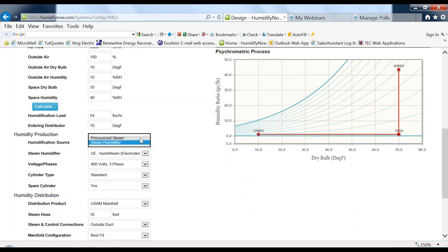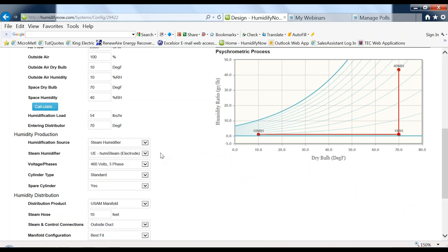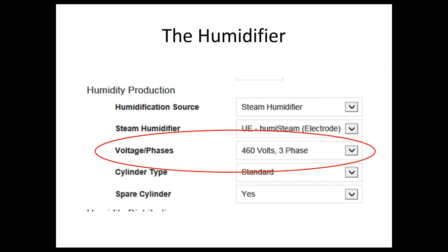There are different types: steam or pressurized, as we just discussed. These are the three types of Carel units that produce steam — and remember, this is atmospheric steam, not pressurized steam. One of the things often overlooked when putting a project together is making sure you know the actual voltage and phase at the project site, so you select the right voltage and phase for the humidifier when it's manufactured.